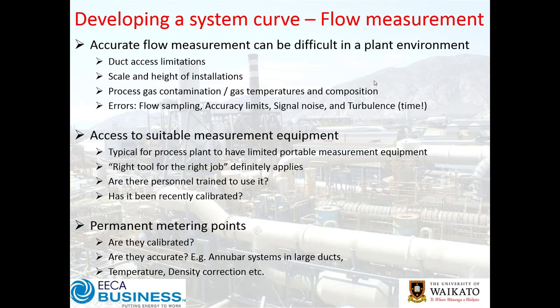Getting good spread between measurement points is also important, and the accuracy of our measurements comes into the mix. Accurate flow measurement is going to be difficult in most instances — there will be trouble with duct access, scale, height, and contamination. Possible errors include whether our sampling is representative, whether we can get enough points across the duct, and the limits to accuracy from signal-to-noise on an operating plant.